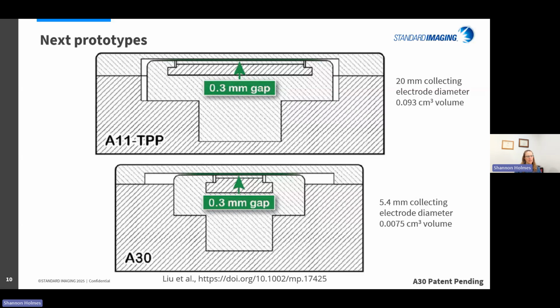And then, does the detector begin to saturate as more dose is delivered? Can it measure a large single delivery, and if so, up to what value? Eventually, it will saturate. I don't know what that value is, and it will very much depend on the time in which that dose was delivered. The electron transit time for these types of air gaps with this electric field strength, I think, is on the order of 3 to 5 microseconds. And so that's going to play into the actual saturation value. I'm sorry I don't have a number for you, but those are some of the things that play into that.